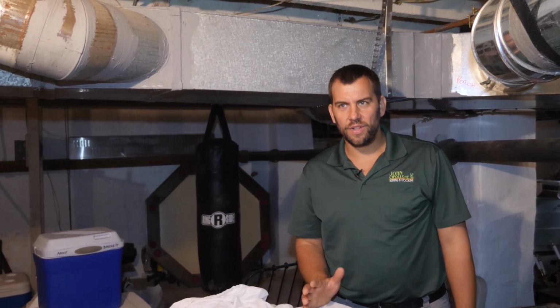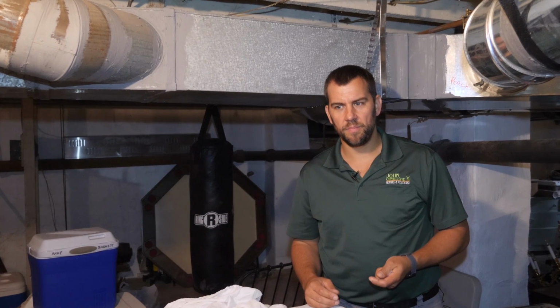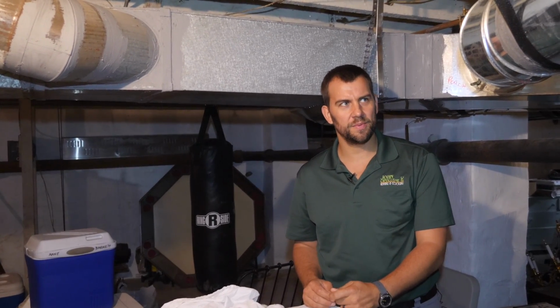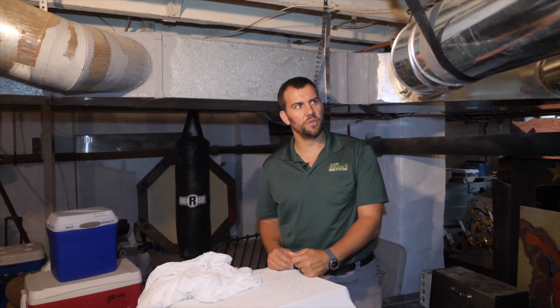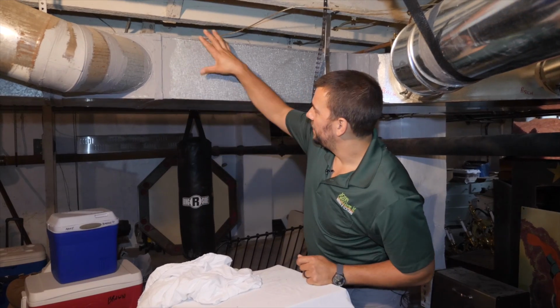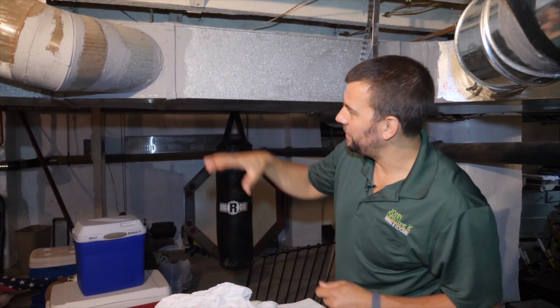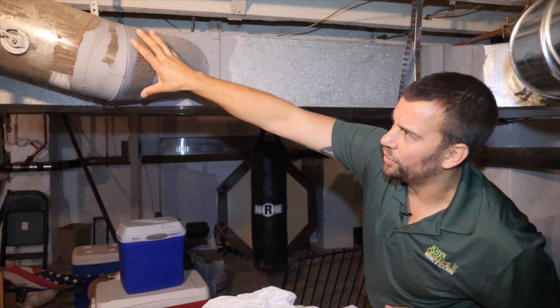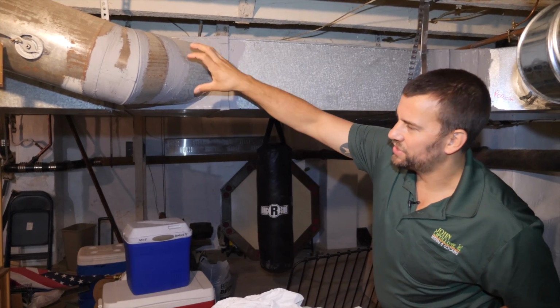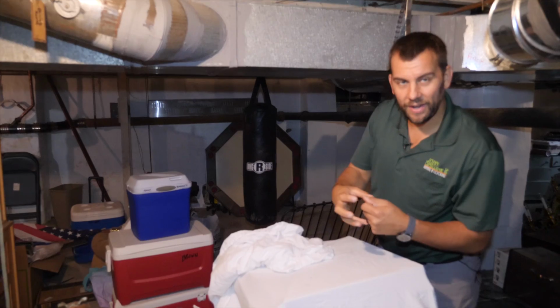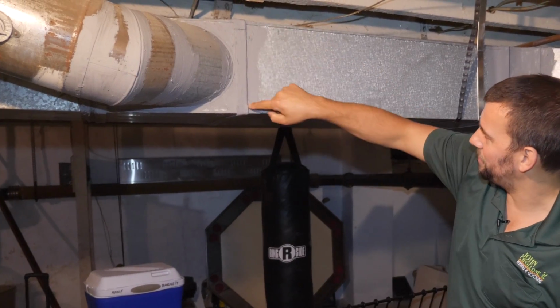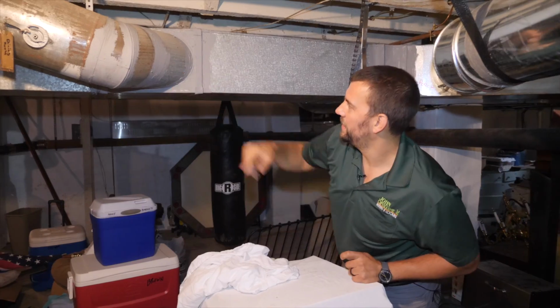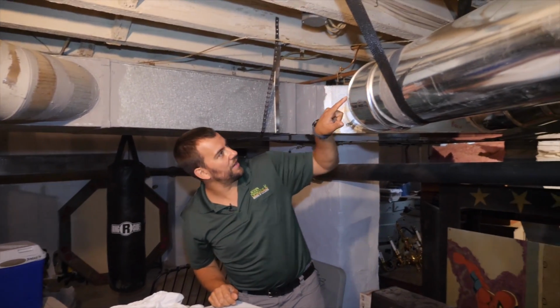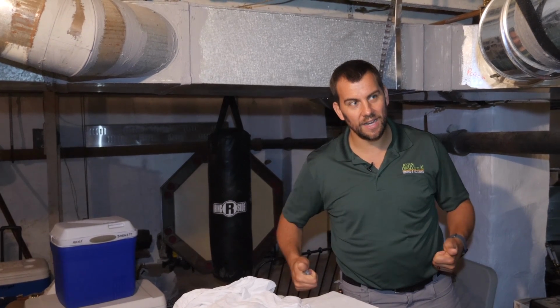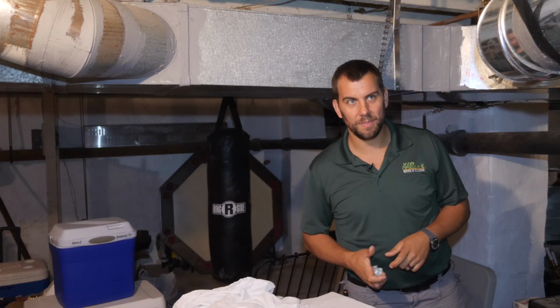When you have ductwork, you get a lot of leakage out of the duct seams. According to the government, ductwork leaks anywhere between 15 and 30%. So one thing we do is seal the ductwork. You can see it's put together using seams and metalwork—this is old ductwork, but the same principle still applies. Certain fittings are put together to create a joint, and that joint tends to leak. So we use a mastic to paint over it. As you can see, all this has been painted or caulked, as well as the newer ductwork. It makes a huge difference in getting the heating and cooling to the actual space that's used, instead of the basement being the warmest spot in the house.